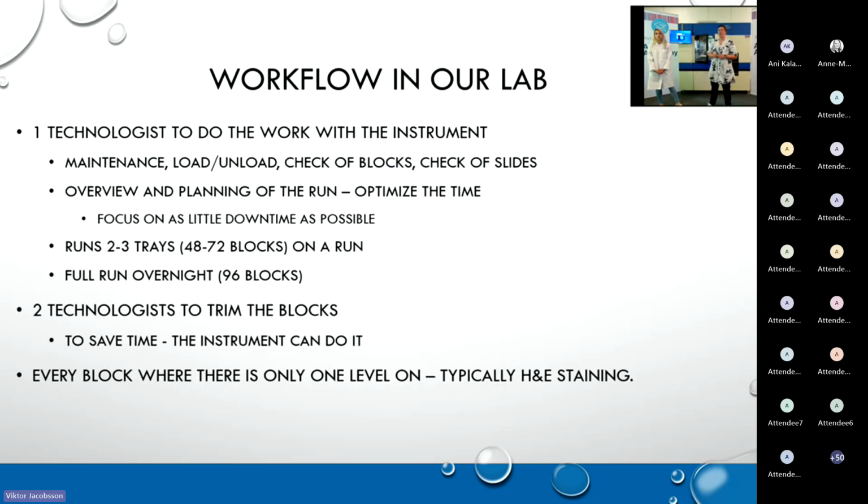So back to a little bit about our workflow in our laboratory. It's just to show how you can manage to get a high output for your laboratory and how many technologists you have to use. We have one technologist working on the instrument through the day. That technologist will do all the maintenance. In the morning, they do a big maintenance of the instrument, and then there will be some small maintenance when you do your runs. They will do the loading and unloading, check of blocks, check of slides. Is the slide quality like we wanted? Is there something for retry, etc.?